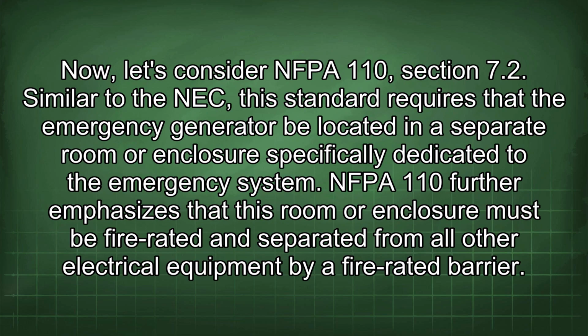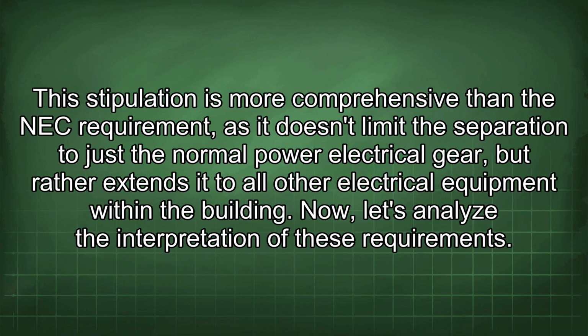Now, let's consider NFPA 110, Section 7.2. Similar to the NEC, the standard requires that the emergency generator be located in a separate room or enclosure specifically dedicated to the emergency system. NFPA 110 further emphasizes that this room or enclosure must be fire-rated and separated from all other electrical equipment by a fire-rated barrier. This stipulation is more comprehensive than the NEC requirement, as it doesn't limit the separation to just the normal power electrical gear, but rather extends it to all other electrical equipment within the building.